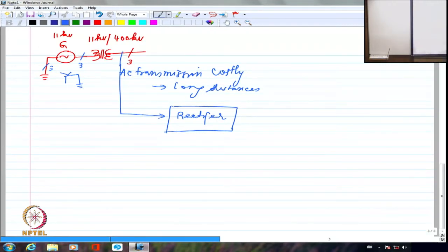So we use a lot of thyristors in series. Normally that's what we do. So whenever I'm talking about this rectifier, this is going to essentially use a large number of SCRs in series. Now the rectifier has rectified the voltage, so I'm going to have a plus and I'm going to have a minus.